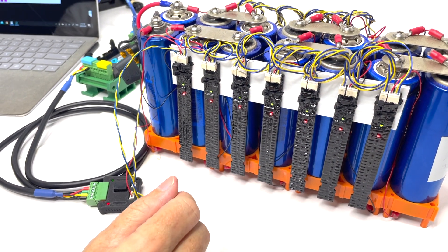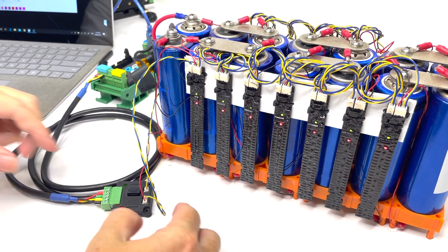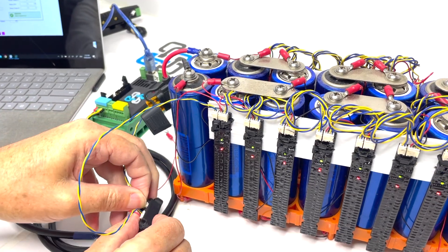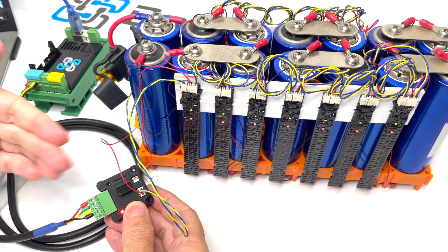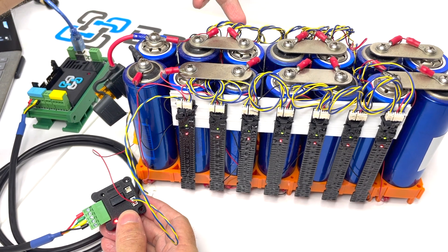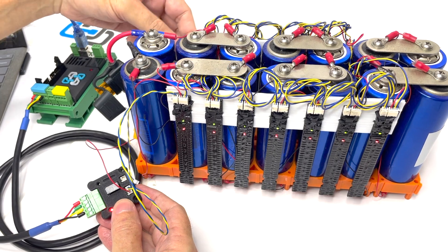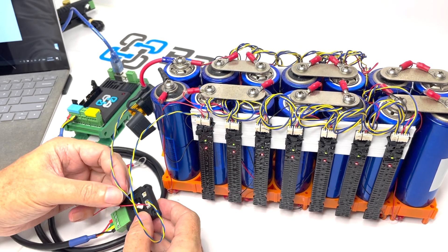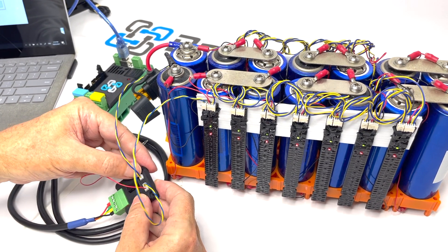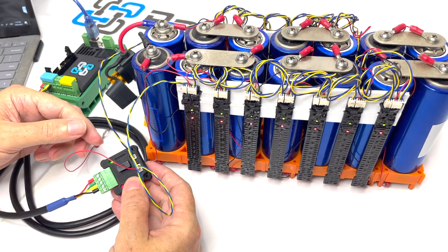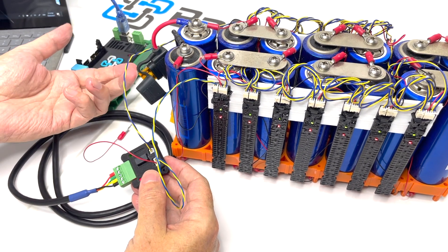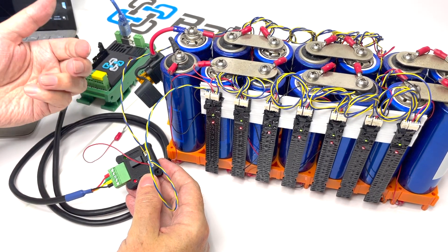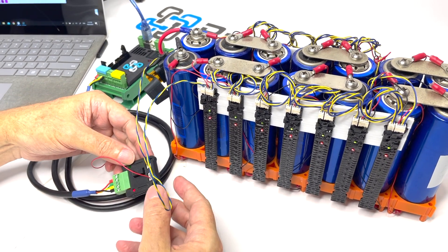Now, the other common scenario you'll hear that the people are saying that there's a network problem is that it's talking all the way through, but the last one is not getting the green LED. So we'll unplug this one. So it's looking like that. Now, at that point, if you're not sure what's going on, then don't just pick the last cell and just say that there's a fault. Grab the cell before it liked what we jumped in the other location. We go back one cell and we plug it in. So I'll just grab that and now we'll plug that one back in. All right. If we get the green LED while we're on network tests, then we know that that last cell has some sort of cabling loom issue as we've jumped it and we can move around the problem. And sometimes switching a LongMon around or switching a cable around helps you determine was it a cable, a LongMon or something or other else. All right. We've now confirmed that we've got communication.